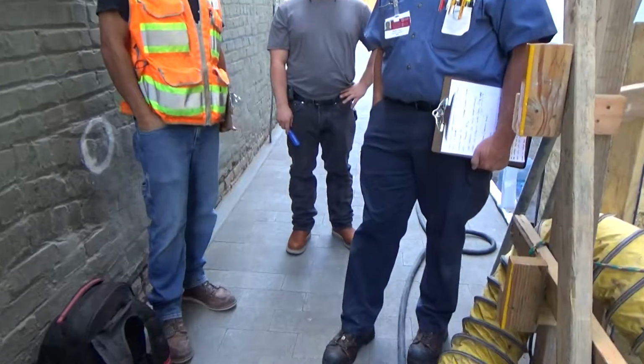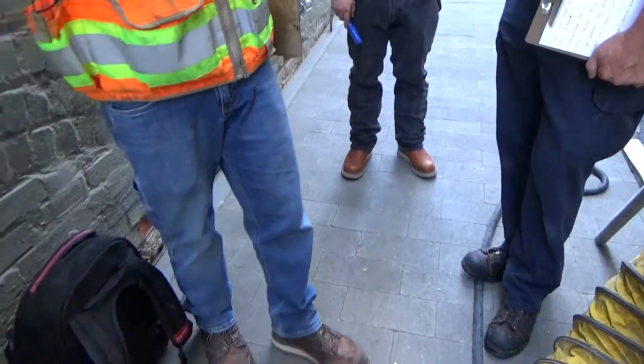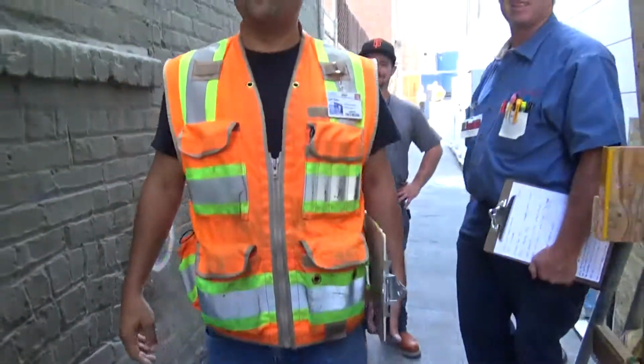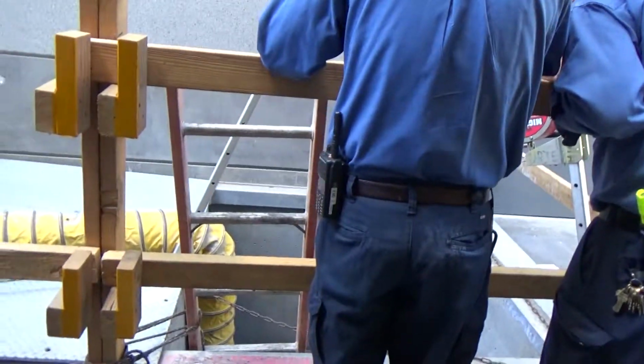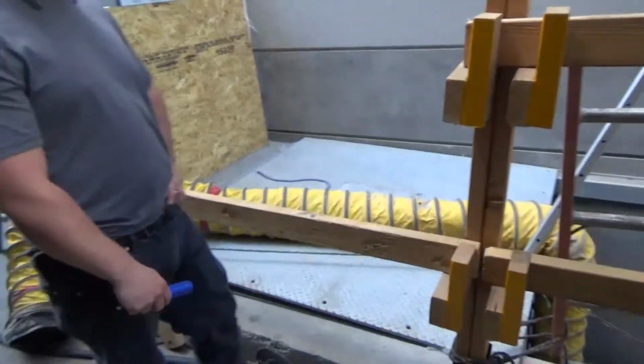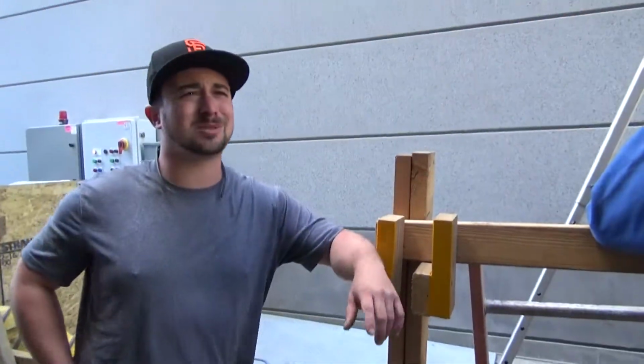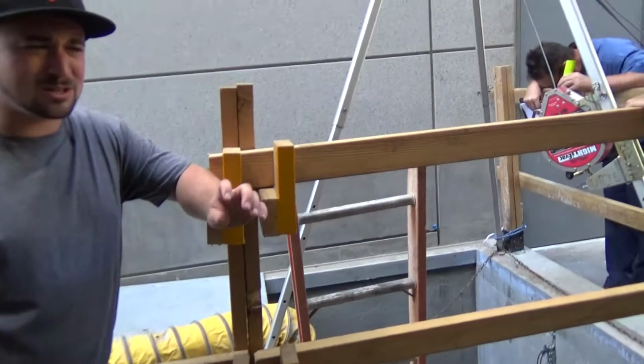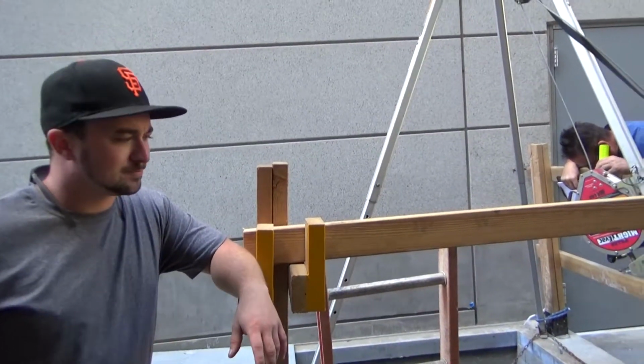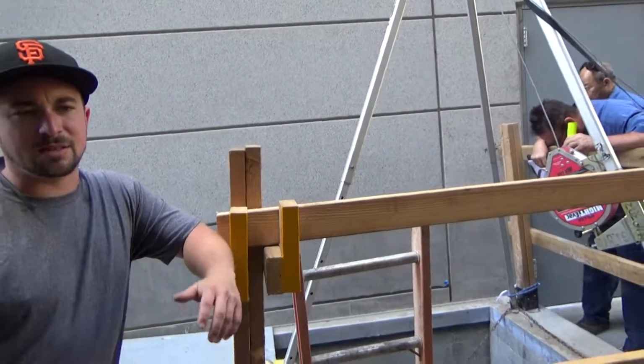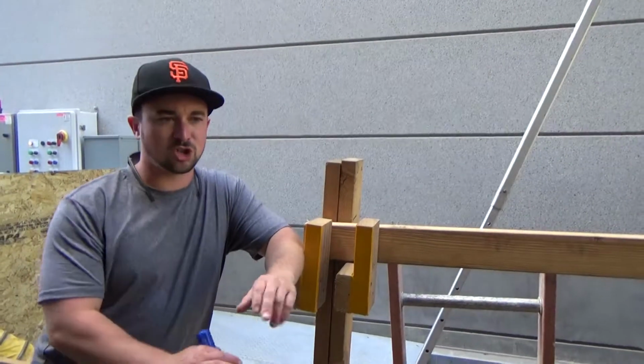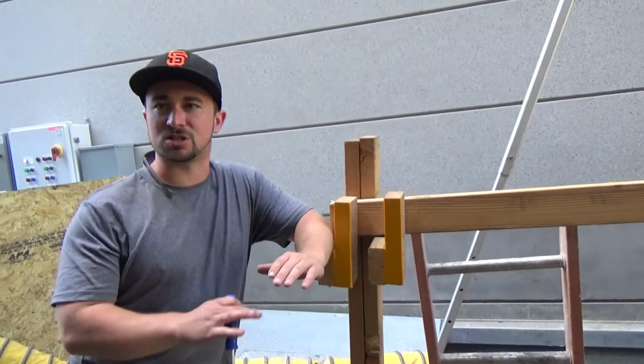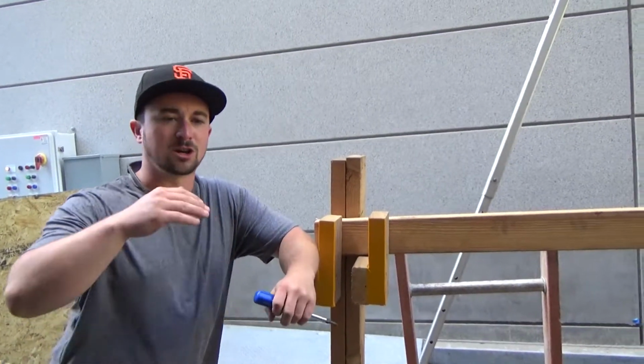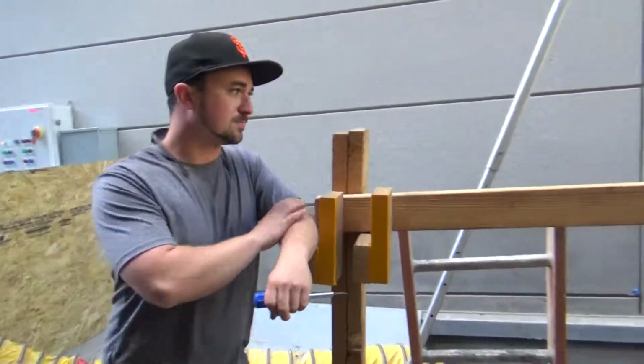Do you know what levels the pumps are at? I just threw that paper out. The floats? Yeah, basically the floats. It was like 20, 24, 30, and 36 or something along those lines. They're both the same. Pumps are raised up, I think, an inch or two, but either way they're per the manufacturer. The whole thing is, when the pumps shut off, the lowest point of that motor is still submerged. We just want to make sure it's not dry, right at the bottom of that motor. Exactly.